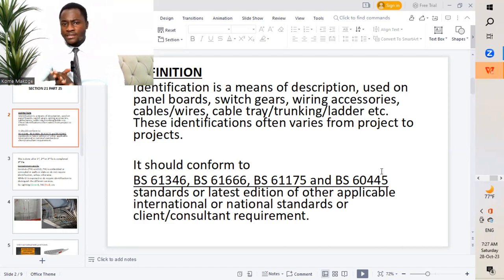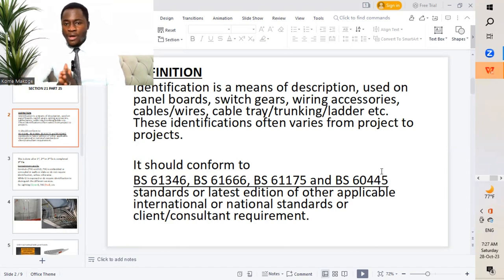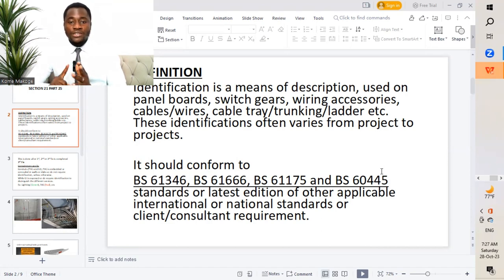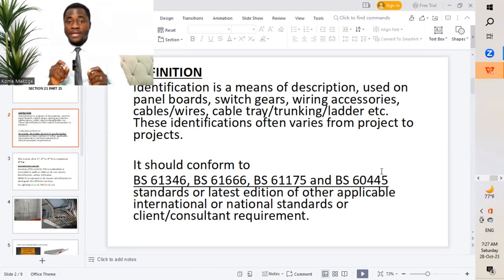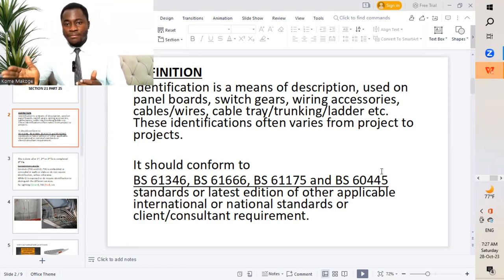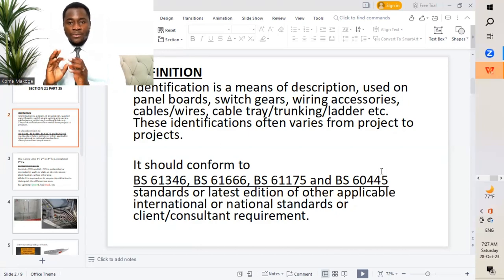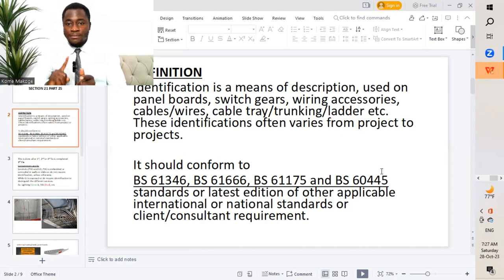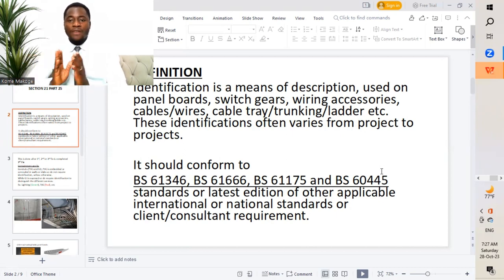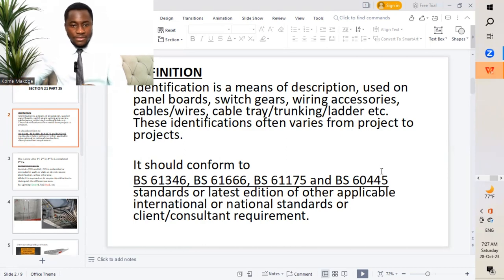You will notice that this different identification varies from different projects. I'll give an example whereby we have our first fix — GI conduits and PVC conduits which are installed on the soffit or probably on the slab — which will have different colors to identify the different services. So while we carry out maintenance, we get to understand that we have probably fire alarm, lighting control, lighting system or normal lighting, emergency light, power, public address system, CCTV camera. So we get to understand that this conduit has been installed for this particular service, which is very important.